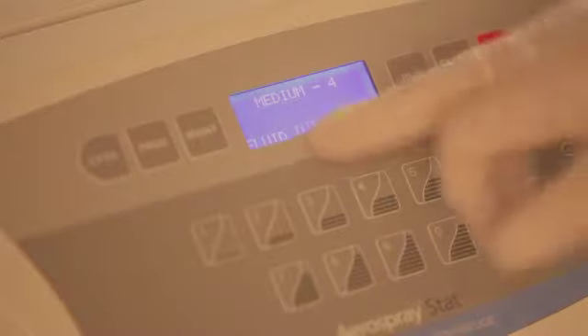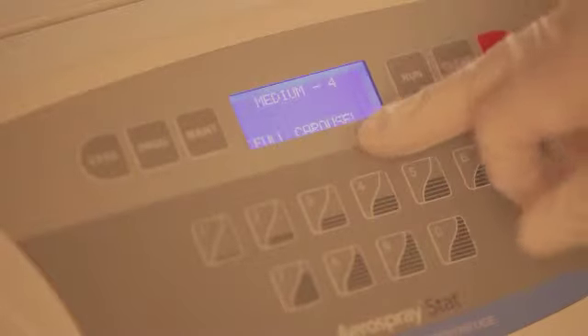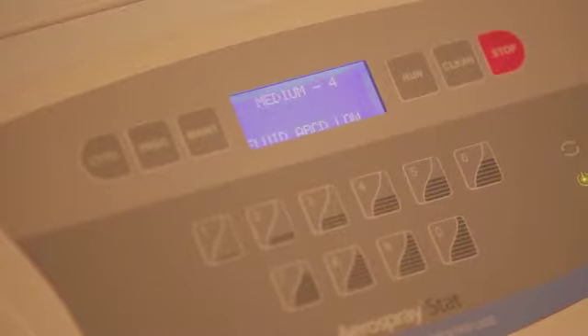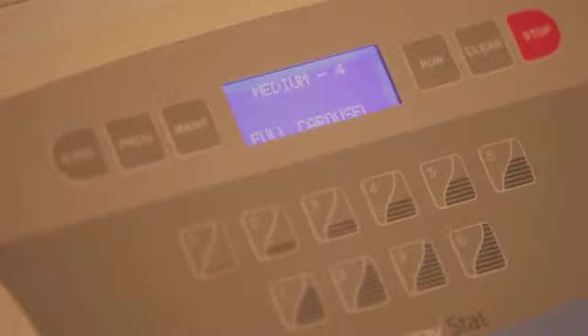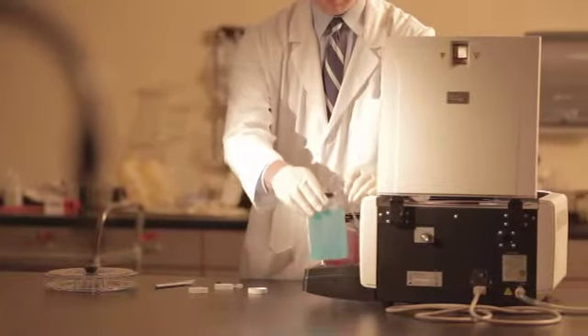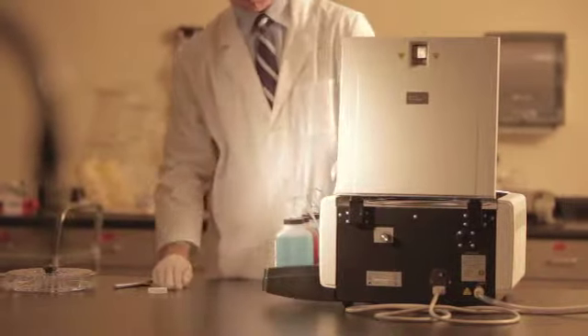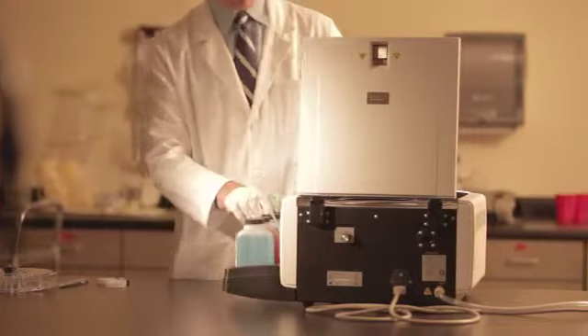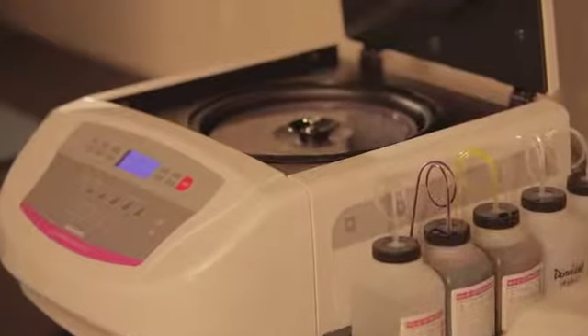With the reagent bottles not in the tray, the bottom line of the screen should alternate between reagent A, B, C, D, low, and full carousel. This line will alternate like this if one or more of the reagents is low. It is now time to place the bottles in the reagent tray. The stainer is now ready to spray reagents after the pumps are primed. Step 5. The reagents are sprayed out of nozzles onto microscope slides while the carousel spins.